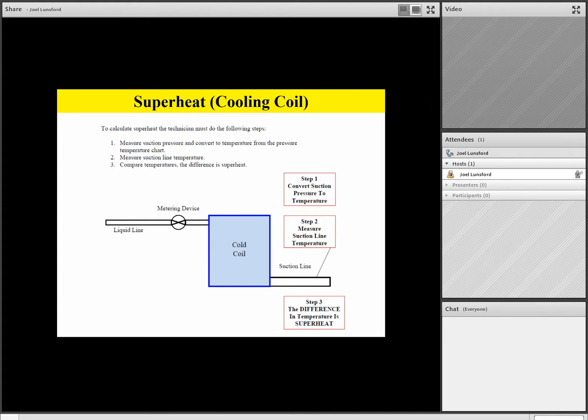And remember, team, the only conditions that a cold coil can ever be in are flooded, there's too much liquid in there, normal, about 10 to 15 in the cooling mode and about 4 to 15 in the heating mode, or starved, there's not enough refrigerant in there. So superheat will always help us figure out the condition of the cold coil. Now please write this down before we start doing some superheat practice. Make a note or two on your page or on your handout.